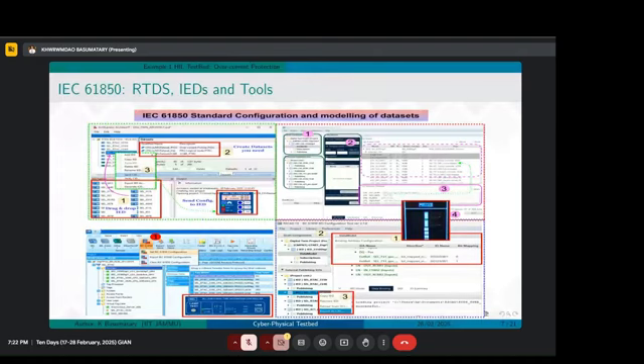After importing, you need to bind the data so that it is available in RTDS, where you can monitor it. Once binding is complete, you need to export the same CID file that was created in RTDS, because you would like to have that data back in the relay, possibly in the RTAC.